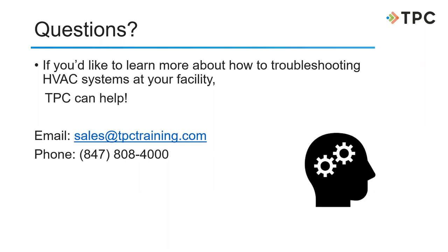Coming in, a question about what would be a common sign that a compressor is not working. I feel like that would be pretty fundamental to anything working, but what are some telltale signs? Pressure difference. Once you hook up your gauges and you do not have established high and low side, one of the first things you want to check is your compressor. And you'll hear the compressor running.